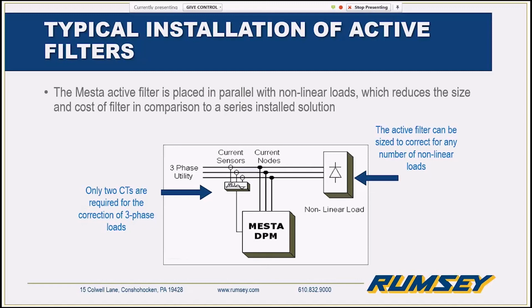back out there. As you can see here, we use a set of 2 current sensors normally, and we can calculate for the third CT, the third phase there. We only need a third CT if there are any single phase line to neutral loads downstream of it. For example, if there'd be lighting loads that aren't separated by a transformer. Normally those are separated though, so we can stick with using 2 CTs.